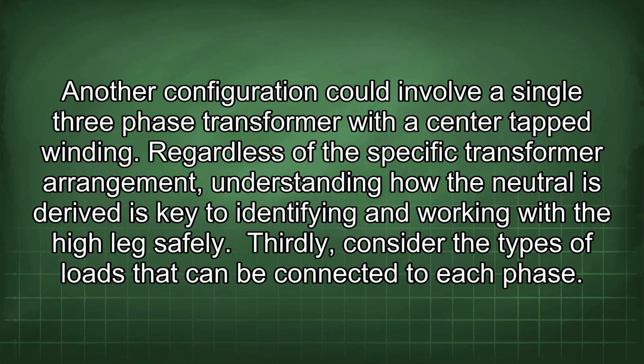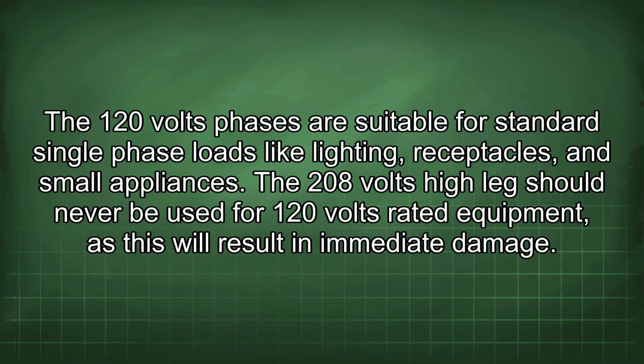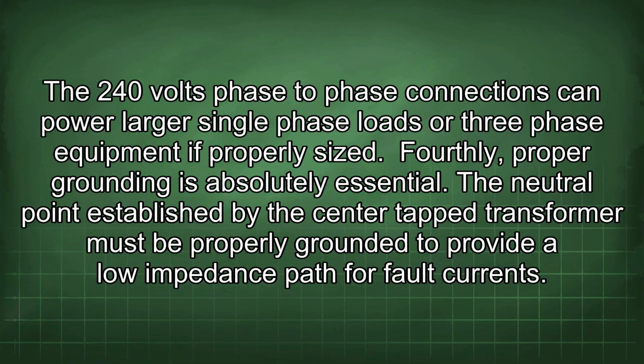Thirdly, consider the types of loads that can be connected to each phase. The 120 volts phases are suitable for standard single-phase loads like lighting, receptacles, and small appliances. The 208 volts high leg should never be used for 120 volts rated equipment, as this will result in immediate damage. 240 volts phase-to-phase connections can power larger single-phase loads or three-phase equipment if properly sized.